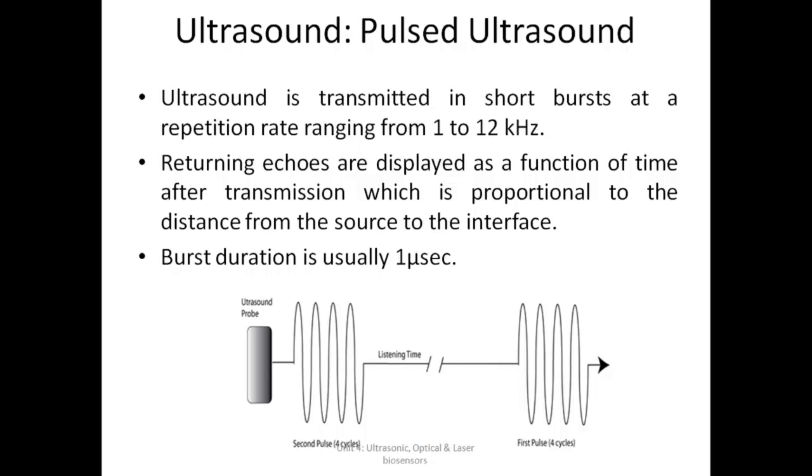One ultrasound pulse goes, okay, then the transducer doesn't transmit anything, it sits idle. In the meantime, the earlier echo which was coming from the striking surface is recorded by the same ultrasound, and it is given to you in the form of electric pulse. Once that is done, the transducer originates another ultrasound pulse, and it gets transmitted.